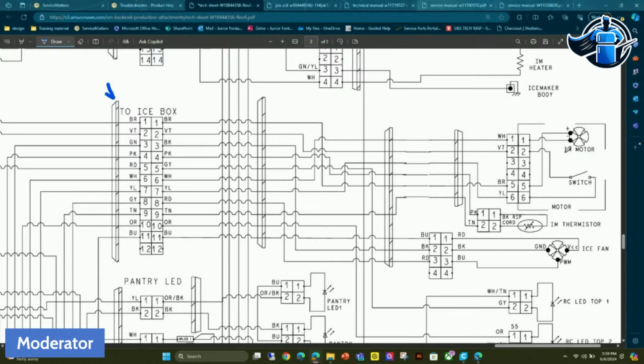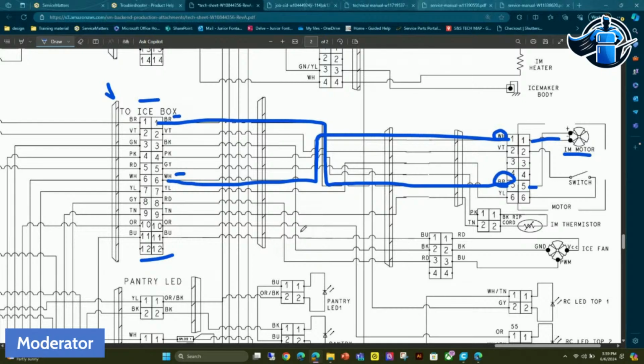So our ice maker is right here. We need to check power to this ice maker, which we can do from the control or by looking at the schematic. It's telling me that at the ice box I should have a 12-pin connector where I can check power. Right here, going to my ice maker, I'm looking for a white and a brown wire on pin 1 and pin 5 right out of the box. I can follow this all the way through to my main plug, which is where I need to be, and they should be the same colors, white and brown.